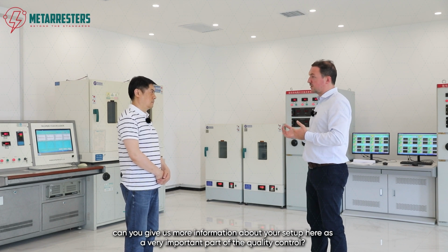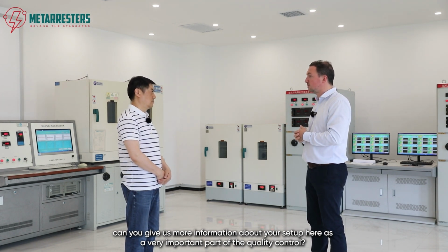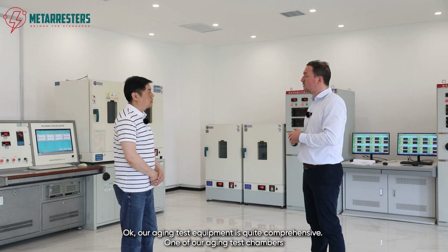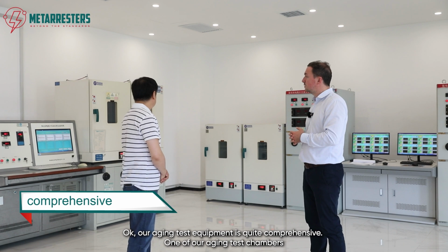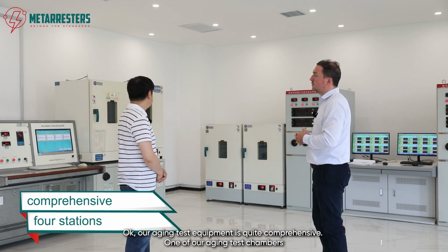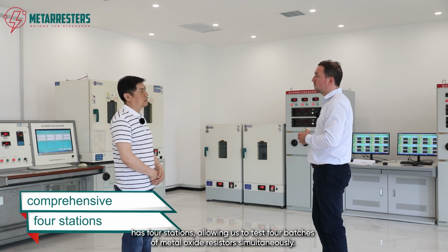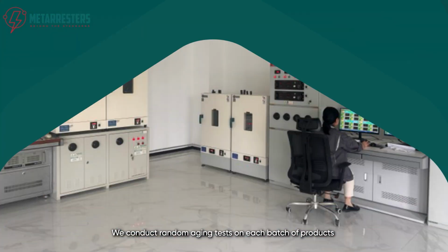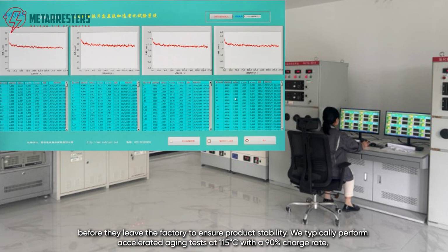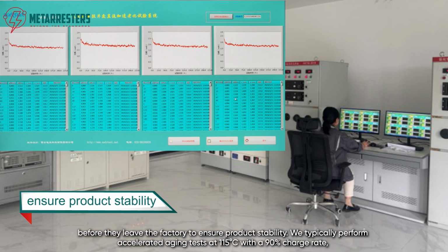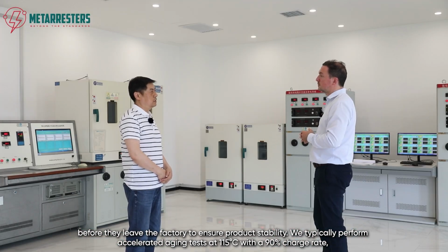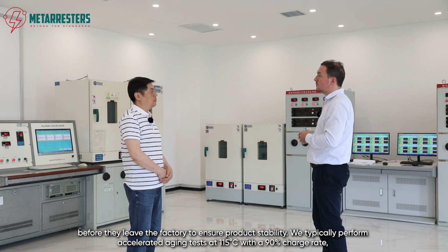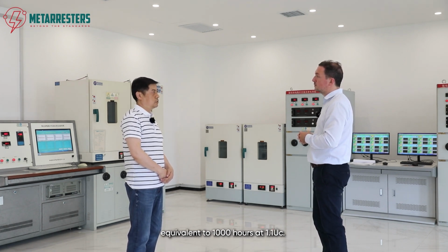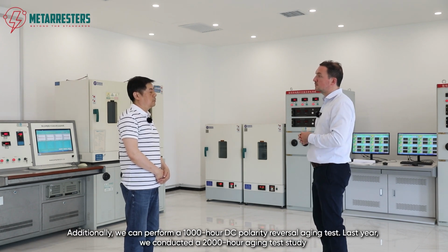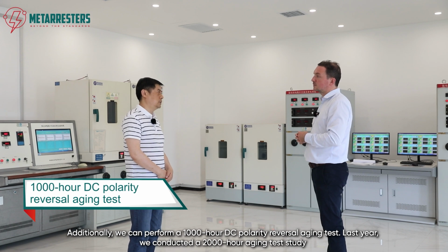Can you give us more information about your setup here as a very important part of the quality control? Okay, our aging test equipment is quite comprehensive. One of our aging test chambers has 4 stations, allowing us to test 4 batches of metal oxide resistors simultaneously. We conduct random aging tests on each batch of products before they leave the factory to ensure product stability. We typically perform accelerated aging tests at 115 degrees Celsius with a 90% charge rate, equivalent to 1,000 hours at 1.1 UC. Additionally, we can perform a 1,000 hour DC polarity reversal aging test.